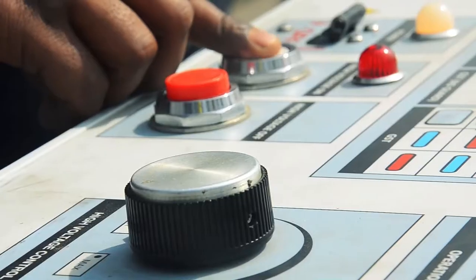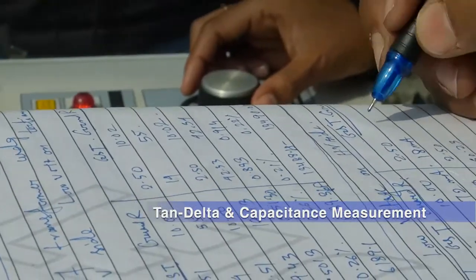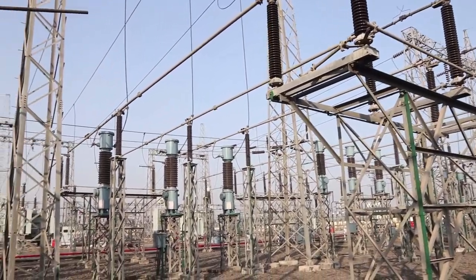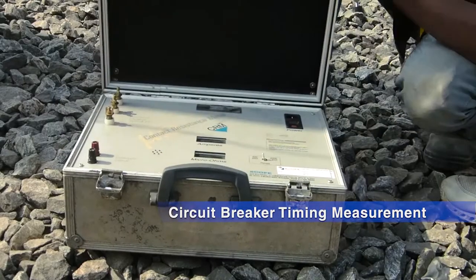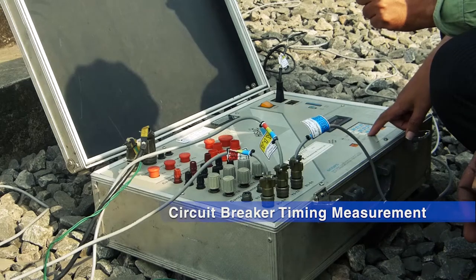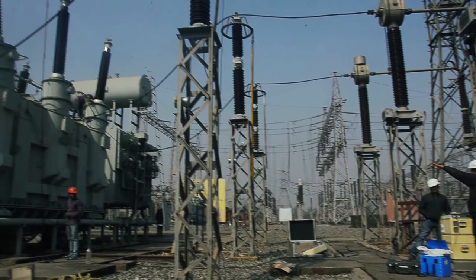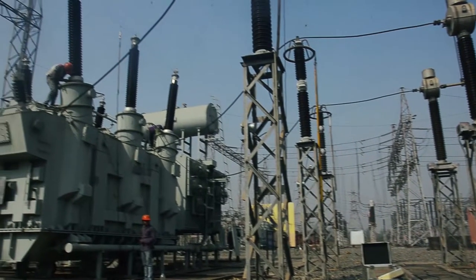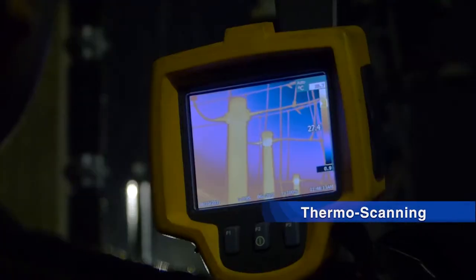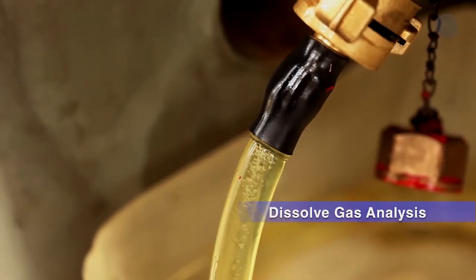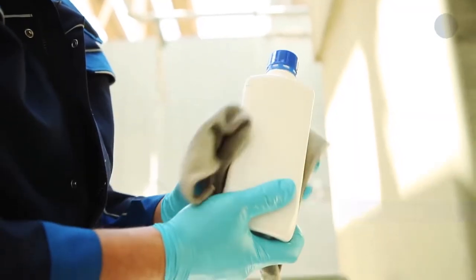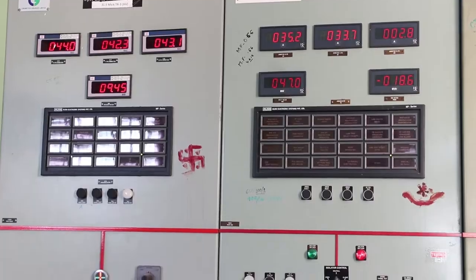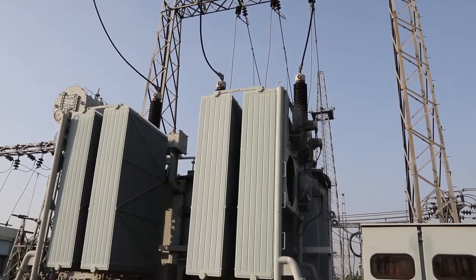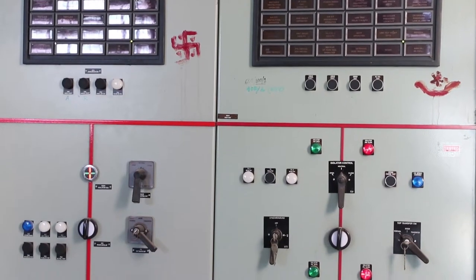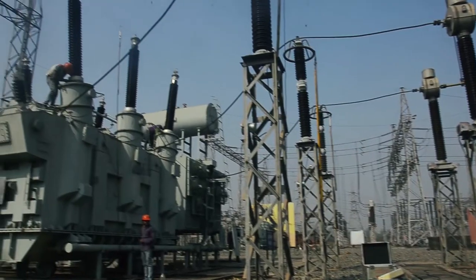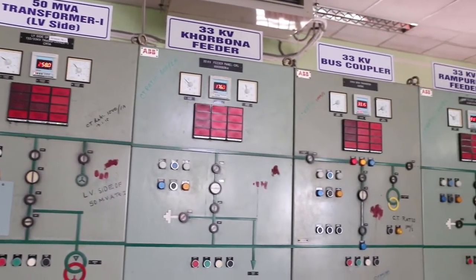to minimize forced shutdown. Some new tests introduced are tan delta and capacitance measurement of power transformer and current transformers. Circuit breaker timing measurement, CRM measurement, lightning arrestor LA third harmonic resistive leakage current measurement to check healthiness of LA, thermo scanning of equipments and connectors, dissolved gas analysis of oil of transformer, sweep frequency response analysis, SFRA of transformers. Periodical testing of protective relays. With introduction of these activities, failure rate has been reduced to a great extent.